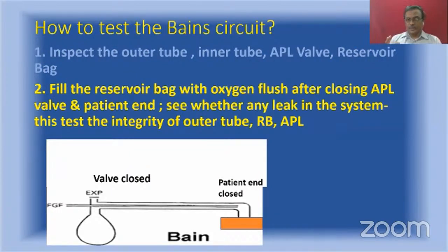That is, you want to check the integrity of the outer tube, reservoir bag, and APL valve. This test is very simple. You occlude the patient end, close the APL valve, and fill the reservoir bag with oxygen flush, and see whether it is deflating by itself. If it is deflating by itself, that means there is some leak. And you can pressurize the system also.